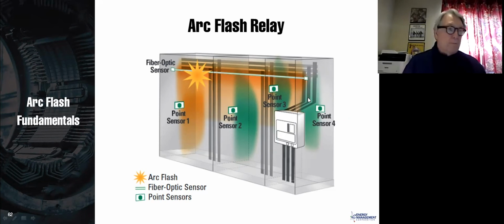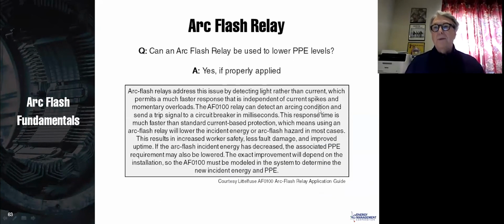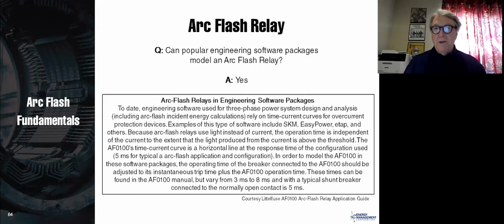It may not help you on the primary of the main breaker. Can you use an arc flash relay to lower PPE levels? Yes, this is very well established, and there is a Littelfuse document to indicate that these are very well established, that you can lower your PPE levels using some of these other methods.